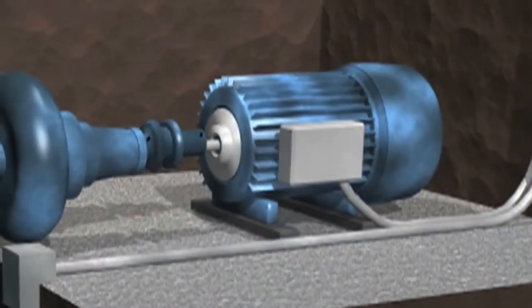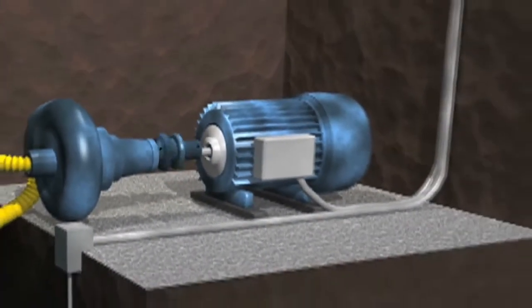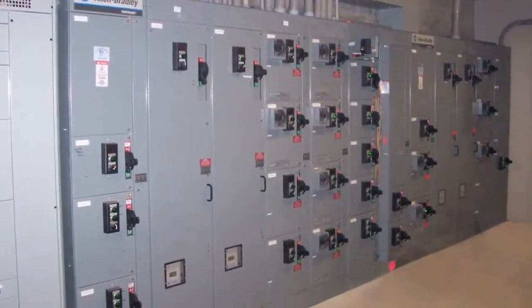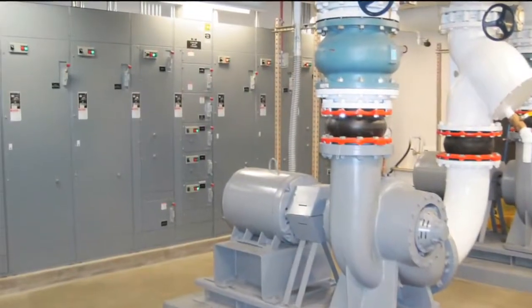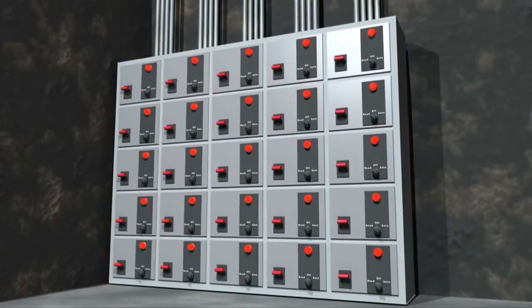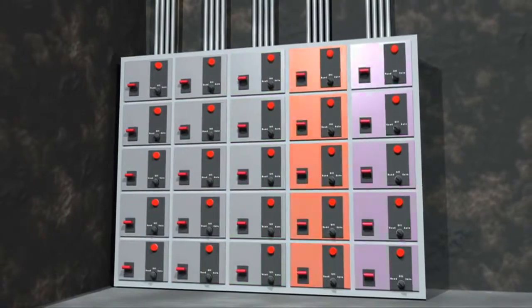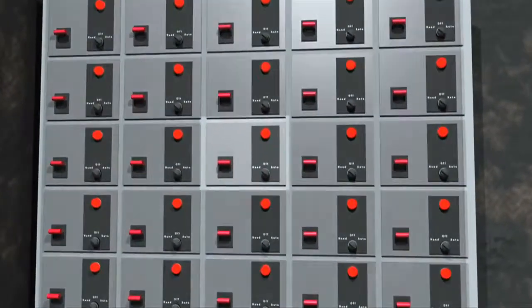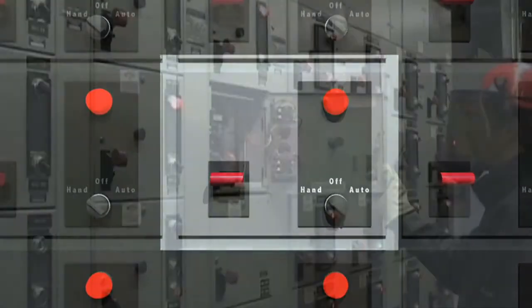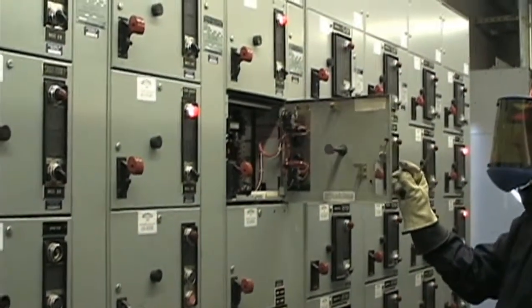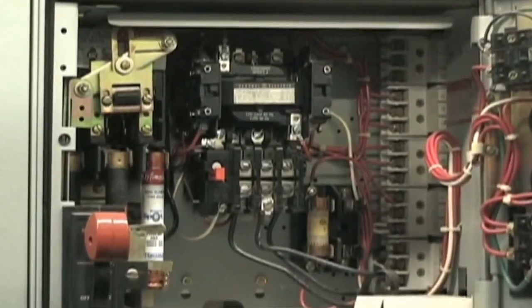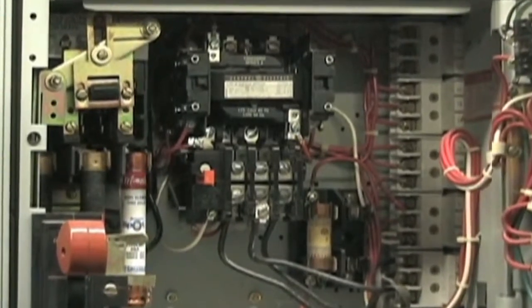In almost every facility, there are electric motors. Motors are used in pumps, machinery, conveyors, elevators, and the list is endless. In order to distribute power to motors, the electrical distribution system has motor control centers, or MCCs. These MCCs are made up of a series of sections. Each section contains buckets. Each bucket is assigned to a specific motor. A MCC bucket contains many things to operate the motor. There can be computer logic boards or PLCs, transformers, contactors, and other control devices to operate the motor.